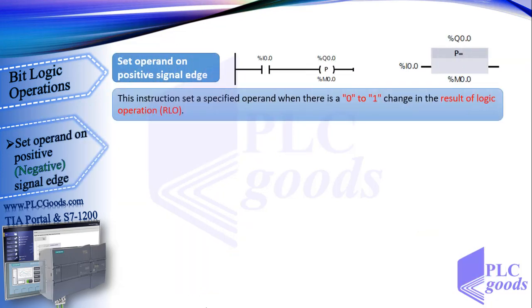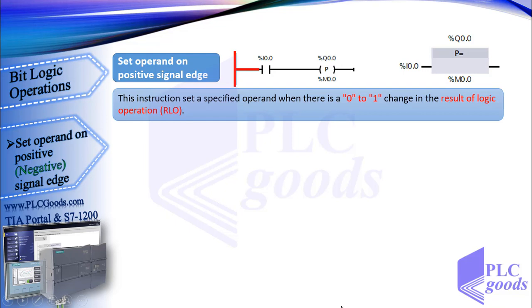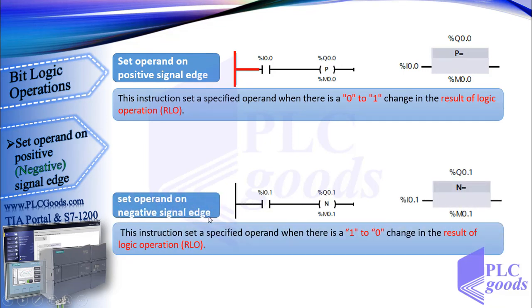Let's see the last instruction in this video: set operand on positive or negative signal edge. Like the previous, but this instruction is used as an output. It sets a specified operand for only one program cycle when there is a zero-to-one change in the RLO. When I0.0 changes to closed, the RLO changes from 0 to 1, which this instruction detects, and changes Q0.0 from 0 to 1 for one program cycle — about 5 ms. Similarly, set operand on negative signal edge works when there is a one-to-zero change in the RLO.